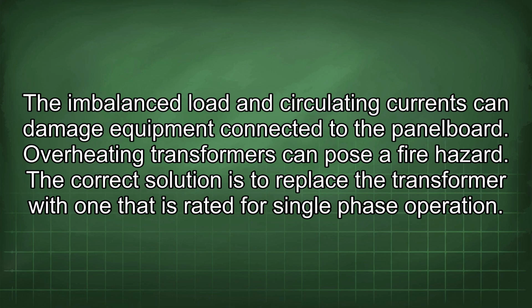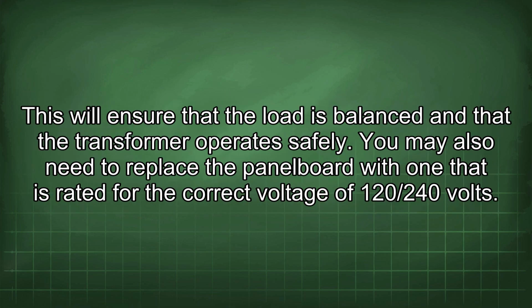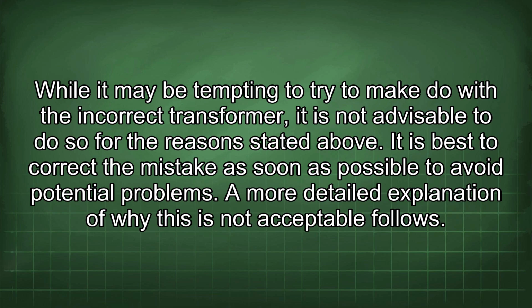The correct solution is to replace the transformer with one that is rated for single-phase operation. This will ensure that the load is balanced and that the transformer operates safely. You may also need to replace the panel board with one that is rated for the correct voltage of 120/240 volts. While it may be tempting to try to make do with the incorrect transformer, it is not advisable to do so for the reasons stated above. It is best to correct the mistake as soon as possible to avoid potential problems. A more detailed explanation of why this is not acceptable follows.